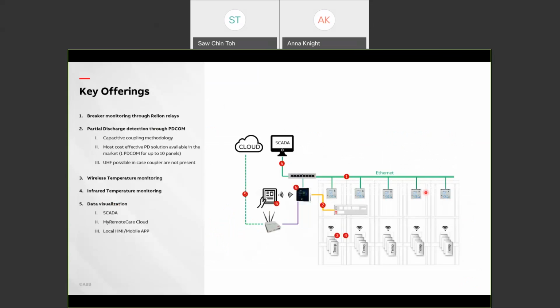Switchgear can also now be made smarter with condition monitoring. We have ABB SWICOM that can offer circuit breaker diagnostics, partial discharge detection, as well as temperature monitoring. This information can then be displayed to the users as a tool to verify the health of the switchboard. It will be shown like in a traffic light system, whether the circuit breaker is live and so on, and will be displayed on the SWICOM unit.